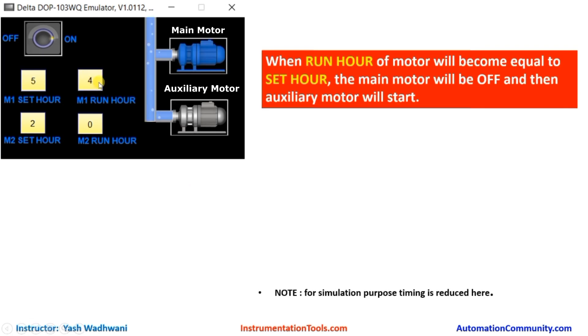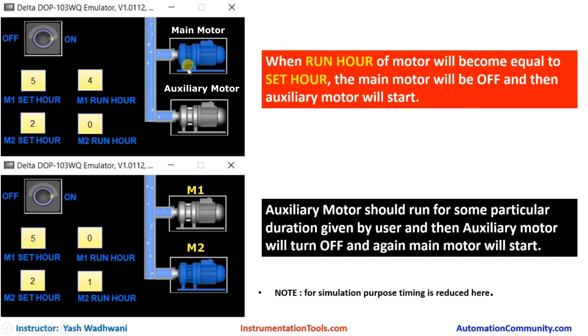When the running hours of the main motor become equal to the set hour given by the user, the main motor will turn off and the auxiliary motor will start. The running hour of the main motor will become 0, because next time it should start from 0, and the running hour of the auxiliary motor is started. It will remain on until the running hour of the auxiliary motor equals the set hour of the auxiliary motor. After that, the main motor will start again.